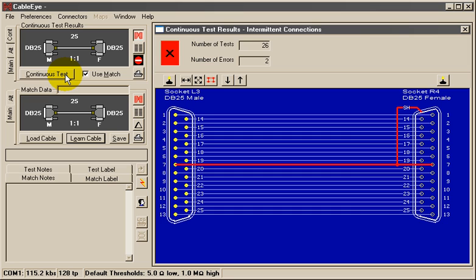During one cycle, every test point is measured with respect to every other point, thus checking every wire in the cable for an intermittent connection, as well as for potential shorts to any unused pins you may have on the connector.